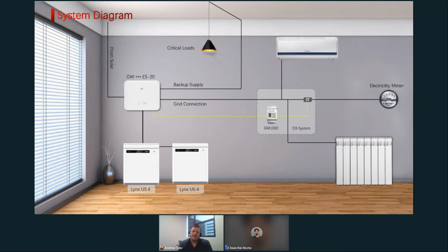Looking at a system diagram, those of you who've previously used our ES Generation 1 will be familiar with this. But just to inform the audience that maybe haven't had this opportunity, the main benefit of a hybrid inverter like our ESG2 would be, number one, to use various sources of power. You'll see on the single line diagram in front of you, we've got solar power, we've got battery power, and then we've got an energy meter, which has a CT clamp attached to it. And that allows you to do, firstly, zero feed-in, as well as load monitoring. And what that also allows is to split the load.